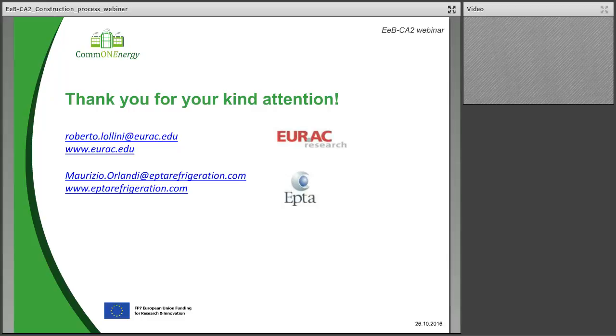We have a case in Norway. Of course, there we started from the point that the building is already well insulated, considering the climate conditions in Norway. And starting from that, the most profitable intervention there was to act on the lighting, for two reasons. One, the electricity consumption for the lighting itself, and the other one is the consumption for cooling. They have a very old lighting system and a very old architecture, almost not using daylighting. So what is happening there is that they have all these old lighting systems switched on all day, and so they also have a cooling load, even if we are in Norway during spring.